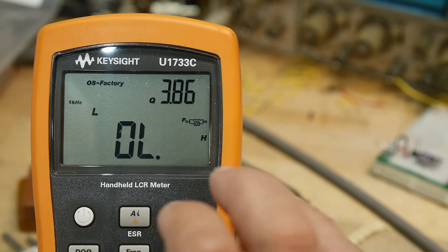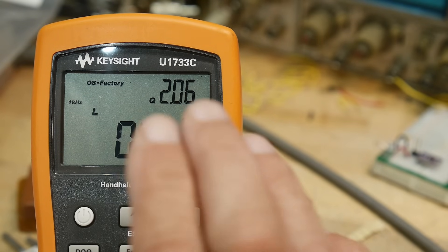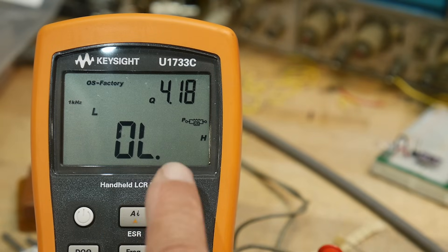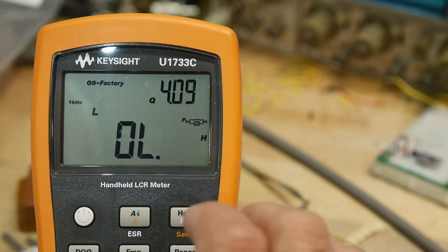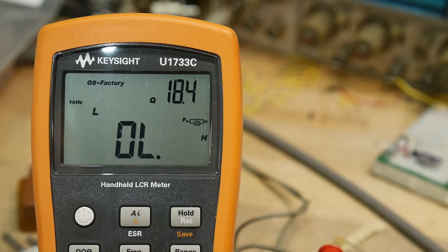If it's below 100 ohms, use parallel mode. And if it's greater than 100 ohms, use series mode. I think I've got that right. Nope. If it's less than 100 ohms, use series. And if it's more than 100 ohms, use parallel. There we go. And let's take a look at what this particular unit does.